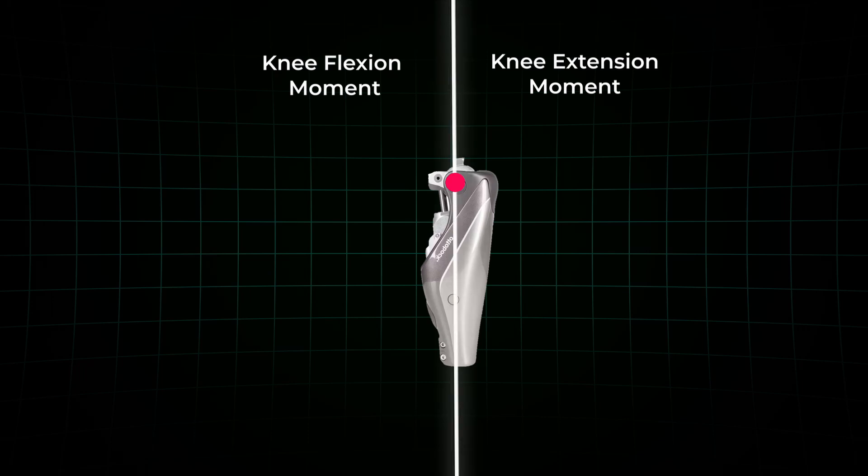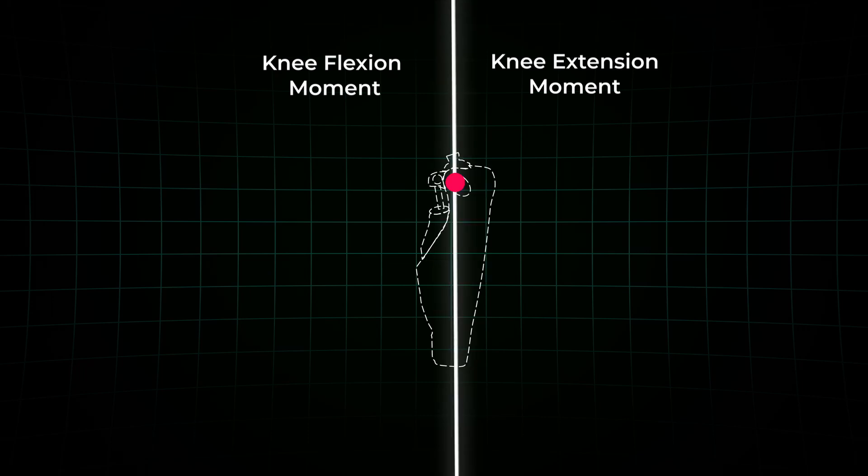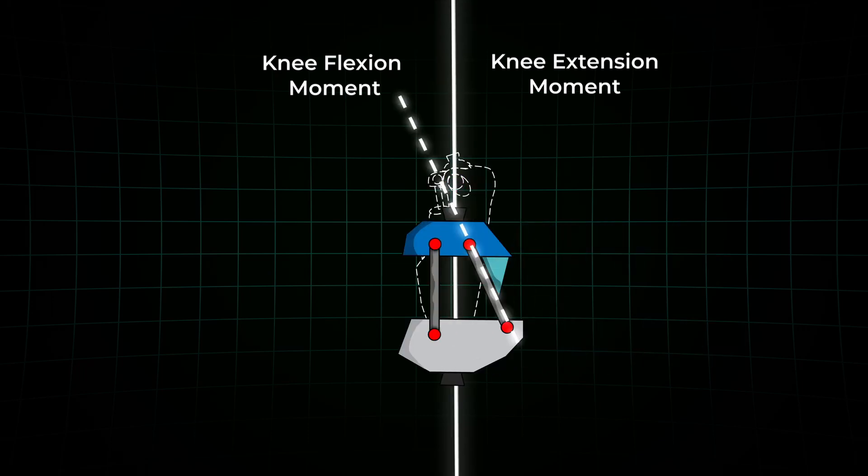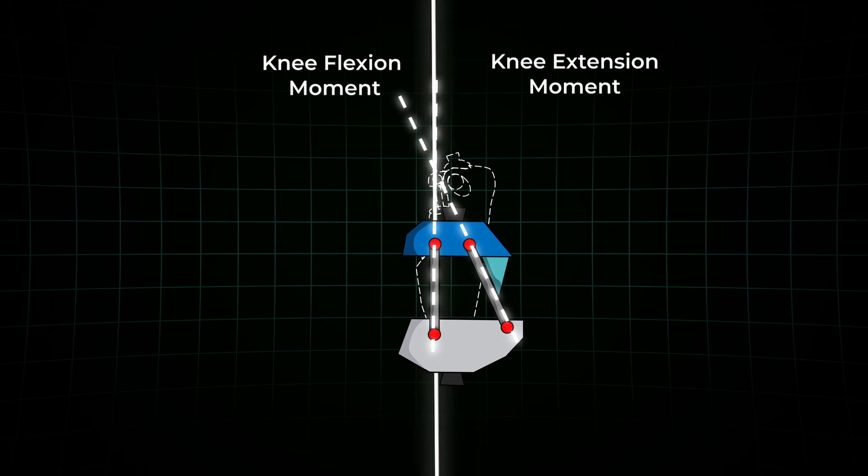In a monocentric knee, the fixed pivot point is always on the same spot. But in a polycentric knee, the instant center of rotation moves. And when the pivot points end up farther behind the knee, this shift increases the amount of extension torque created by the ground reaction force, making it much harder for the knee to buckle accidentally.